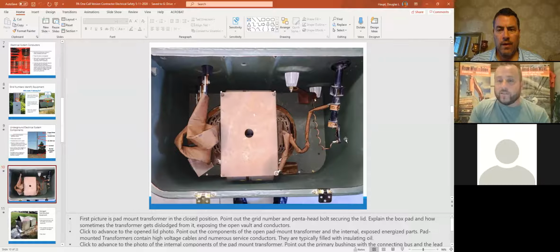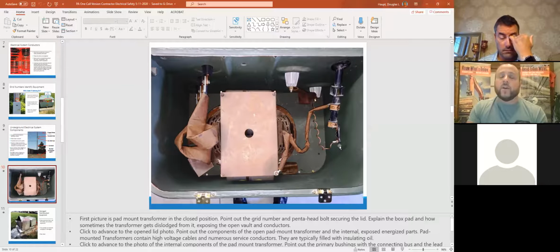But you'll notice this connection from here to the sidewall in the back of the box is about 3 to 4 inches. If for some reason you hit this transformer box and knock it off its base, do not try to push that transformer back onto its base. You don't know what happened inside of here. Could something come dislodged, or did you dent this in and now it's only an inch away from this hot connection? If you hit it with a backhoe, run into it with a truck, knock it off its base in any way, call your electric company.